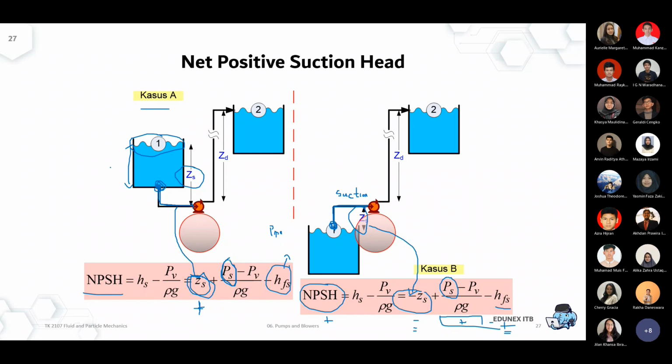or make it a very high elevation. Okay, so let's say the full tank level is 10 meters, for example. That gives you hydrostatic pressure, right? Because that gives you another rho g h. You get hydrostatic pressure by providing this level of 10 meters, for example. That's another 1 bar. Okay, 1000 times 10 times 10, that becomes another 1 bar only by providing a level of 10 meters. So that helps you in a way to prevent cavitation as well.